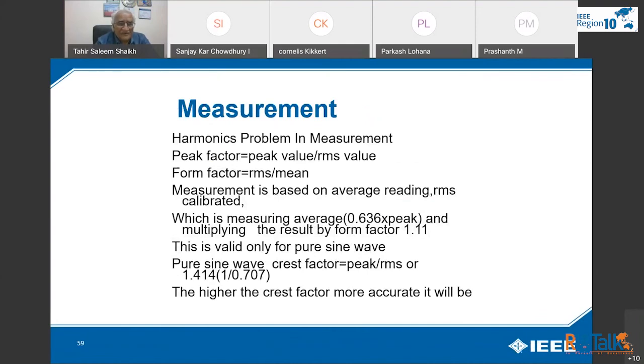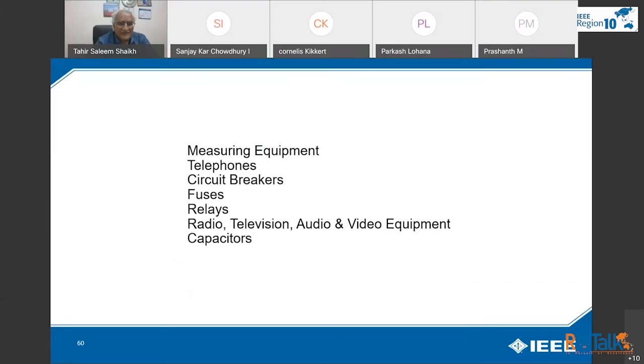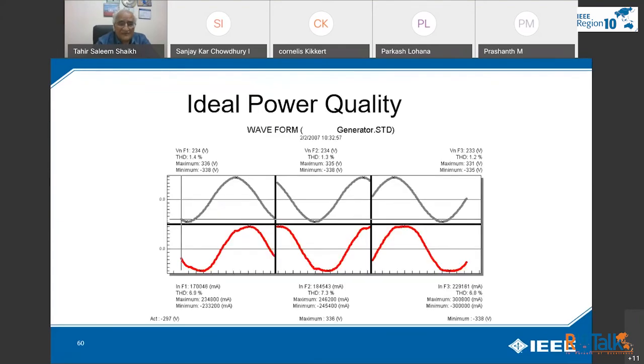Measurement, you can have problems in measurement: peak factor, peak value, form factor. RMS measurement is based on an average reading, and this will give a misleading reading on your meters. Measuring equipment, telephone, circuit breaker, fuses, relays, noises, tripping of fuses and relays, radio, audio and video equipment, capacitor. Even I have seen in certain hospitals the harmonics create so much noise, tripping and image distortion in ultrasound labs. So you have to correct this.